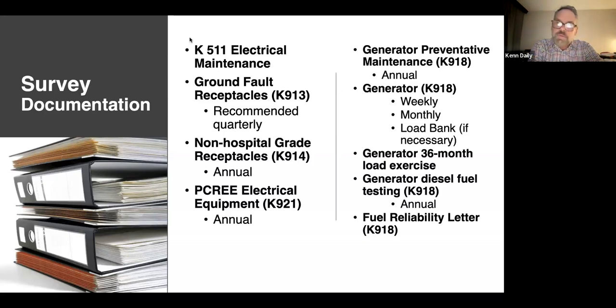You have your weekly visual inspection of the generator. You have your monthly exercise under load, taking your building from pole power to generator power. If you're a diesel generator, you are permitted to use the load bank test as an alternate form of compliance if your diesel generator is not running at 30% of its nameplate rating. Once every 3 years, you do a 4-hour loaded exercise. So it's the same as the monthly exercise, just for 4 hours under load.